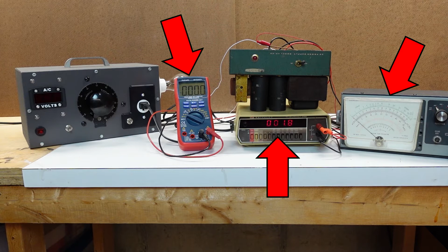The middle meter will measure the medium voltage secondary, looking for around 125 volts AC. And then my trusty IM13 vacuum tube voltmeter is measuring the high voltage secondary, which should be around 270 volts AC. Looking at the scale on the meter itself, that should be just over mid-travel of the needle.